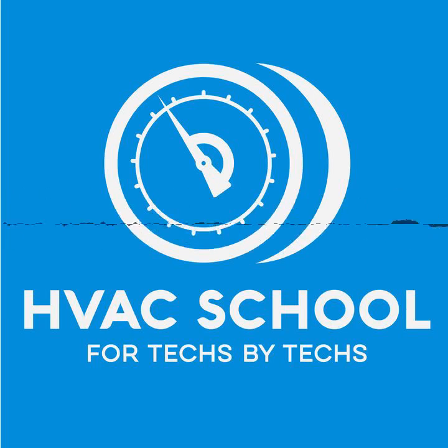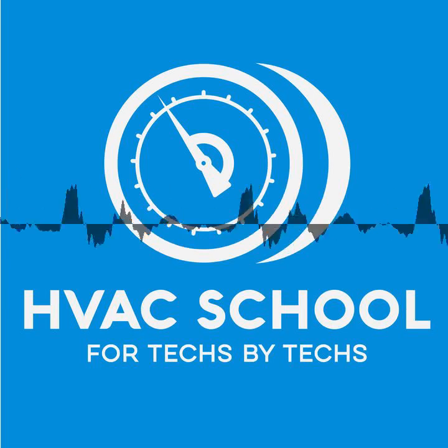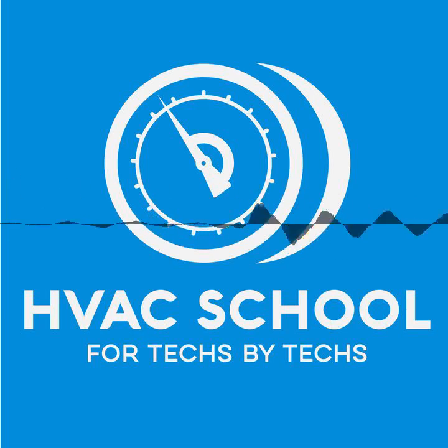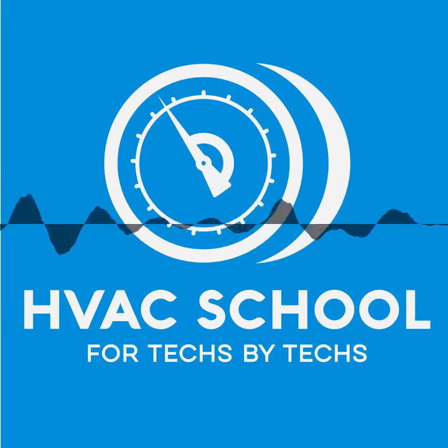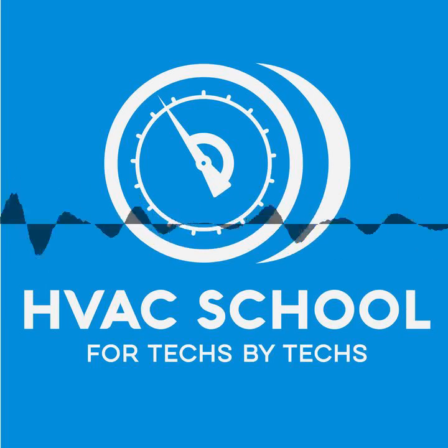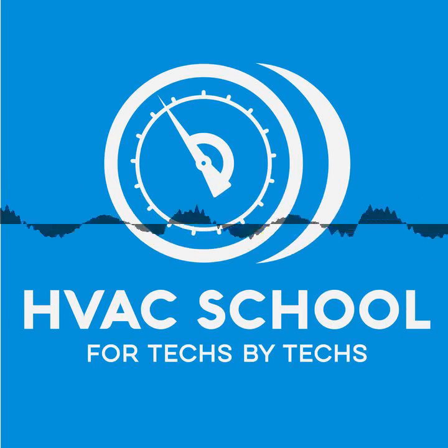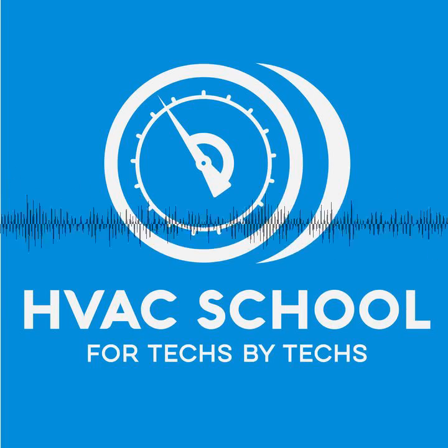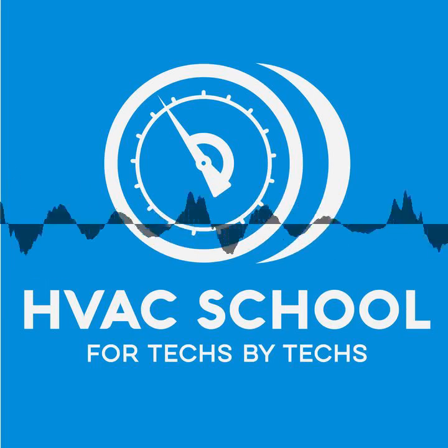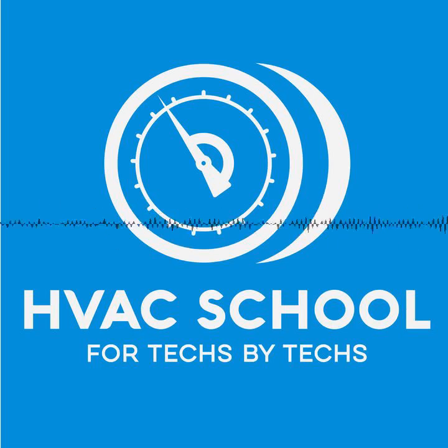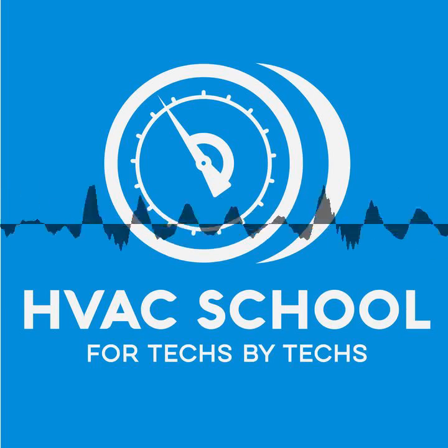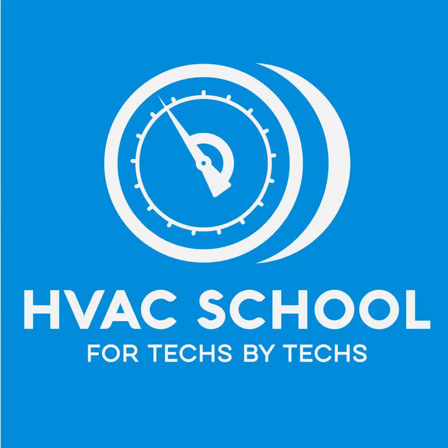If you have a TX valve that has a removable filter in it, you can check that. But even before you get to the TX valve, look upstream. Yes, you've got subcooling at your condenser, but let's turn this into an electrical situation. If you have 24 volts at your control transformer but 0 volts at your control relay, what do you generally do? What's your next step? Right, you have to move down the line and see where you're losing it. Absolutely. I could show you pictures of filter dryers where the last half or three-quarters of an inch is white. And it's not frosted paint that we put on there, it's ice, because the filter dryer is plugged.